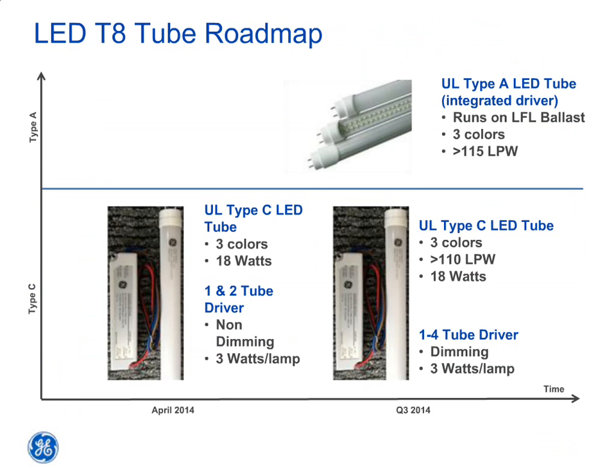When I think about what's next, so again, more variation. Normally, we think of 2-lamp replacements for 2x4 fixtures, again trying to drive down energy costs, assuming that's enough light. Again, these Type C means LED tube with a remote driver. So we're installing a driver separately, disconnecting the fluorescent ballast. It's a great way to ensure compatibility. So going up to, again, higher lumens per watt, more lamps per driver. Kind of a similar parallel to what we saw years ago with electronics, with ballast for fluorescent.